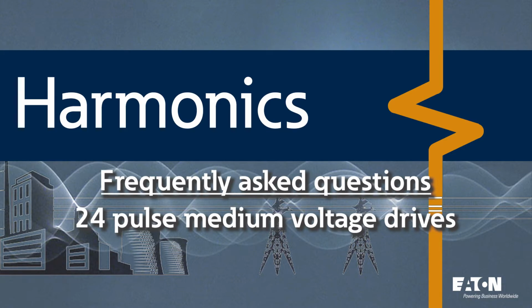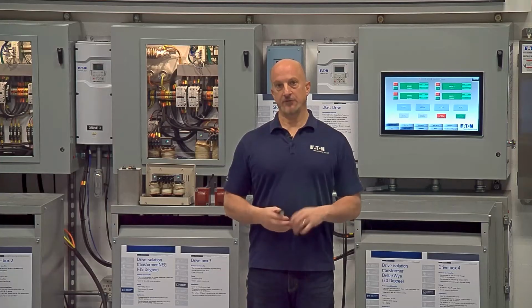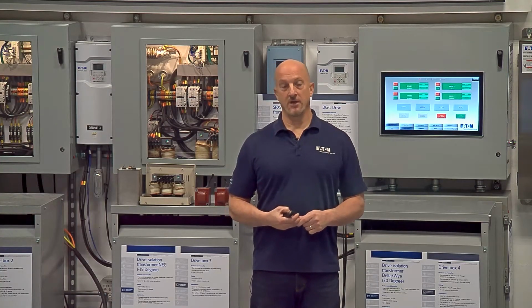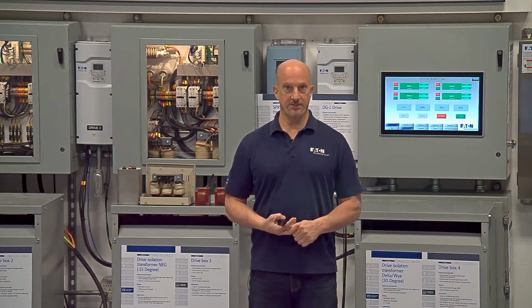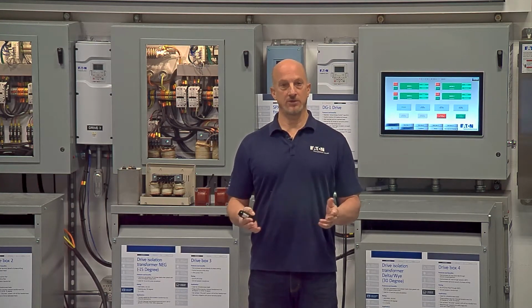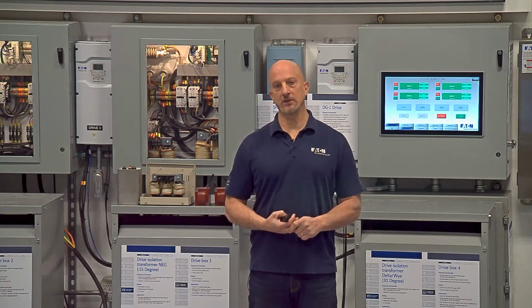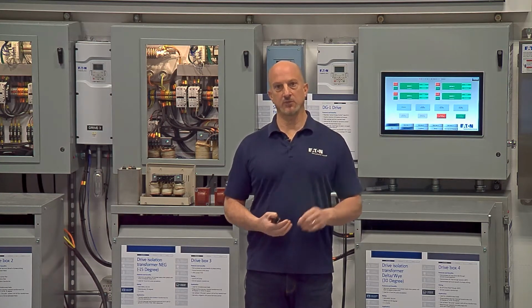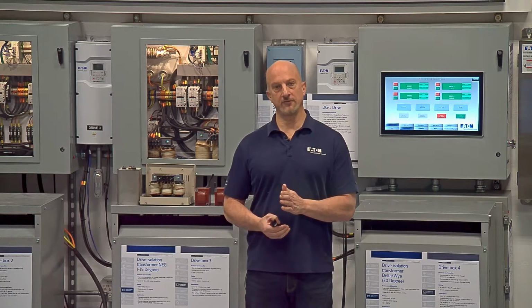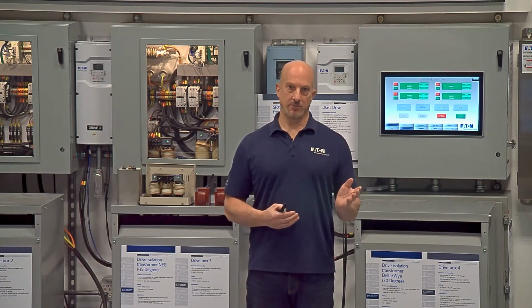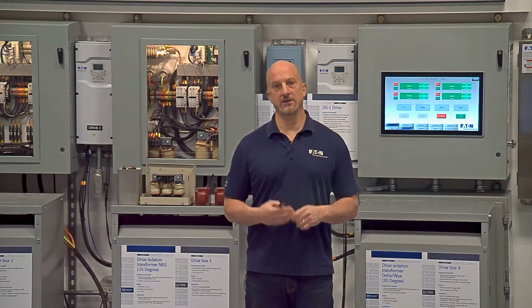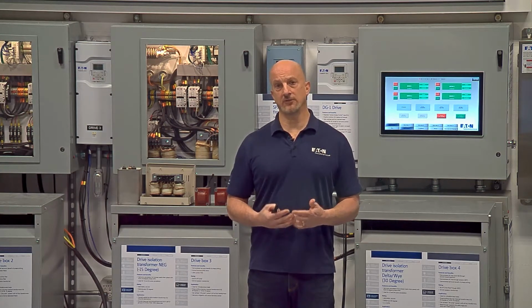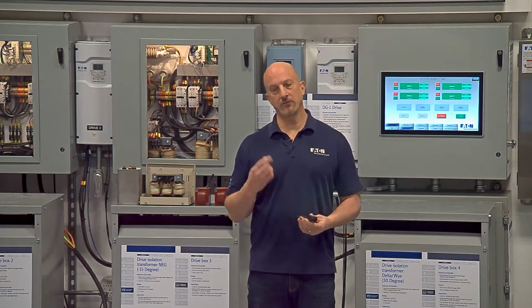So what's a 24 pulse drive, and why do we typically apply them at medium voltage? A 24 pulse drive takes advantage of phase shifting cancellation of harmonics, and using that equation NP plus or minus 1, we're only left with 24 plus or minus 1 harmonics. So 23rd and 25th, 2 times that, plus or minus 1, 47th and 49th, and so forth. And because those harmonics are higher order, the magnitude of the harmonics are very small.